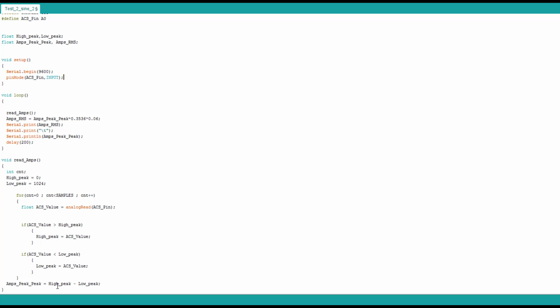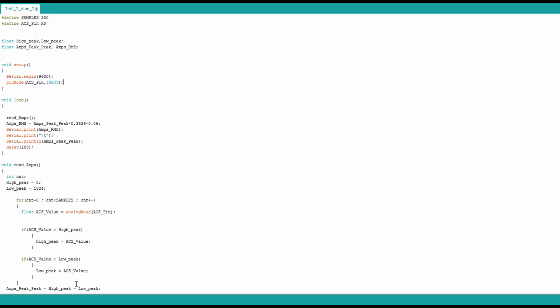So here I do a small calculation, high peak minus low peak. Normally I would convert it to amps by multiplying by 0.3536, which is the formula to go from peak-to-peak to amps. But since I need further calibration, I multiply again by 0.06 just to get the correct values.